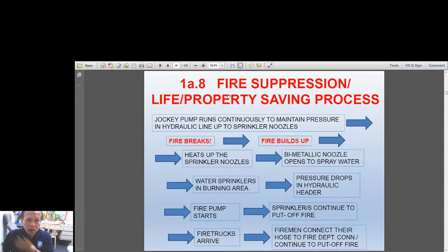The next slide is fire suppression. So after the life-saving process, now we have the fire suppression and life and property saving process. So again, as usual, in a building that has an automatic fire sprinkler system, your jockey pump is always running every now and then in order to pressurize the hydraulic system, meaning the sprinkler system of the building. So the jockey pump runs, and then when suddenly there is a fire, the fire becomes big, builds up, and hits a sprinkler that is just above the fire.